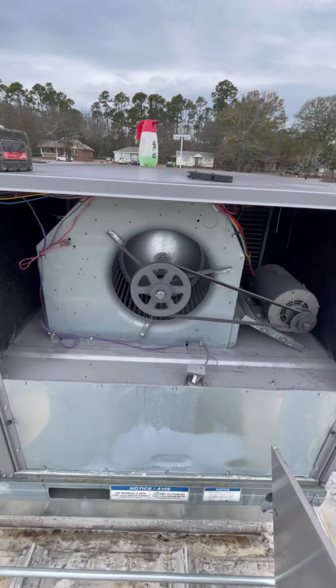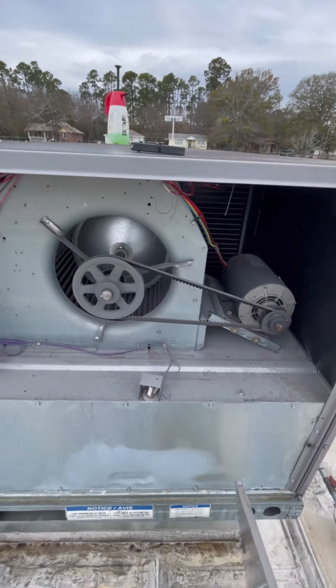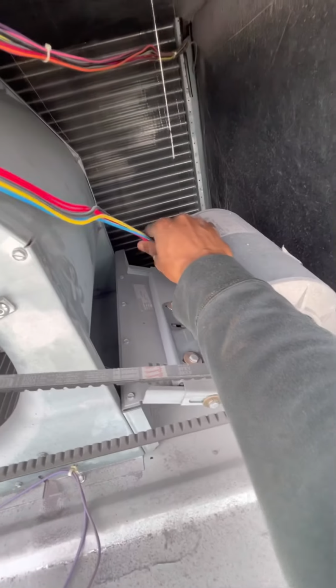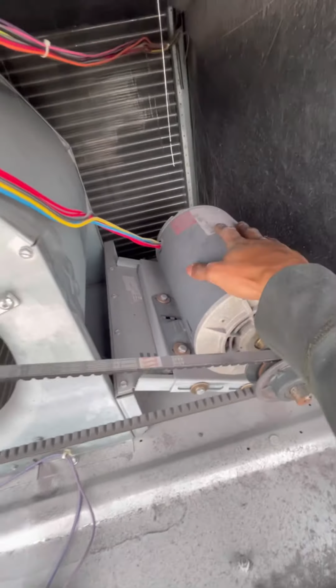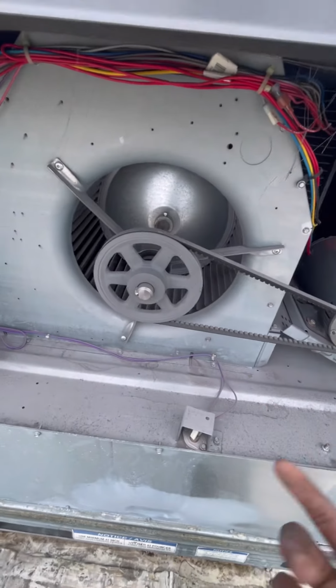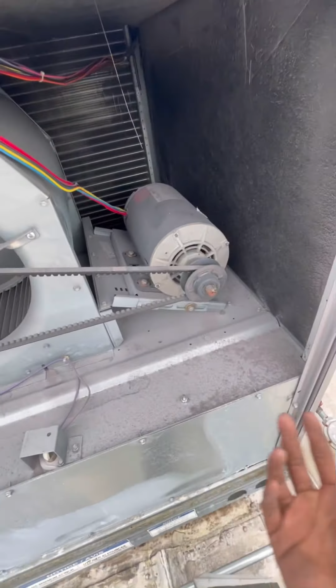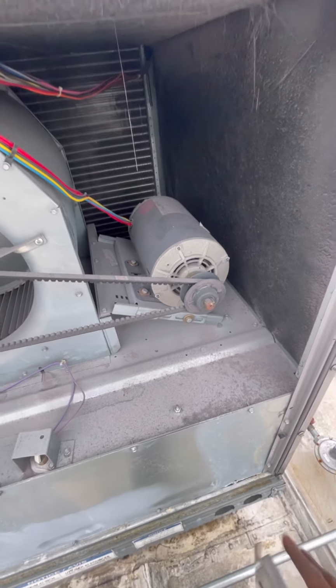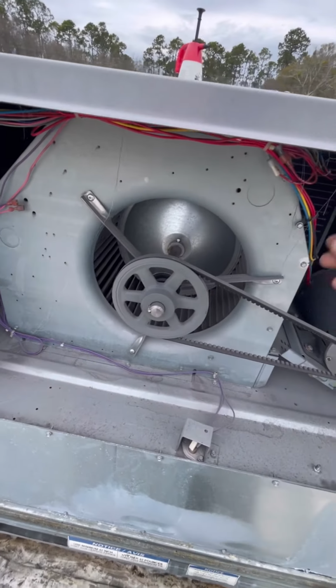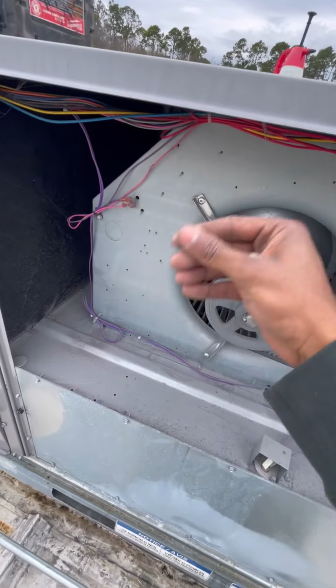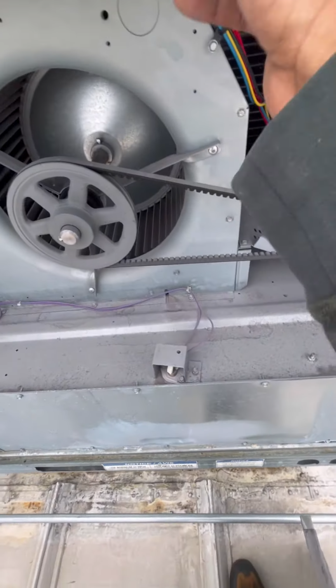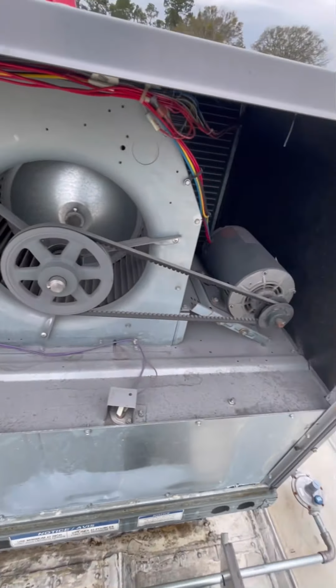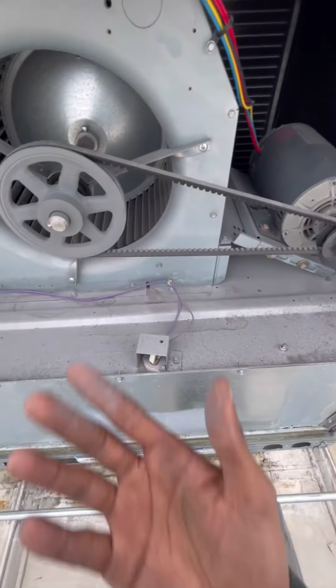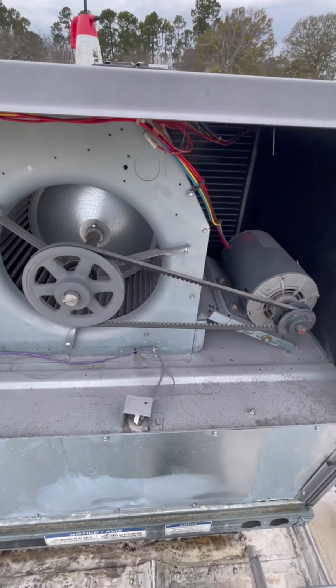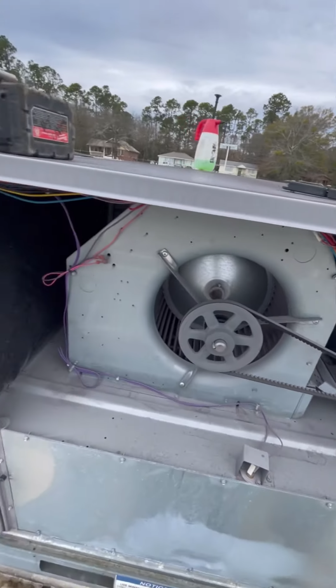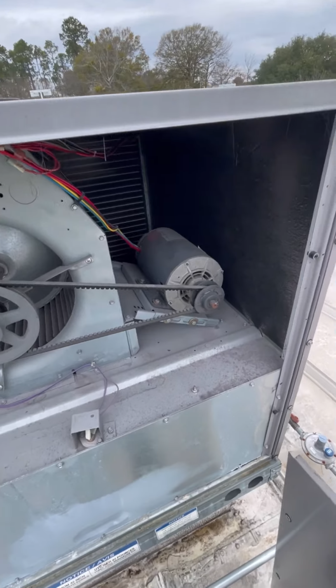So I pulled the blower motor door off, and it looks like we have an ECM motor, and this is where the electronic control comes from, which tells this to come on and how fast to come on and all of that good stuff. But there's no capacitor or anything for us to check, so that's just me being thorough, going the extra step, making sure this thing doesn't have a cap, because I don't want to be a lazy tech and skip a step and then there be a cap, the cap's bad, this doesn't work, and now I'm getting called back here a day or so later, or even later on today. Number 1 rule in HVAC: always be thorough, never skip steps, man, because you'll end up biting your own ass.